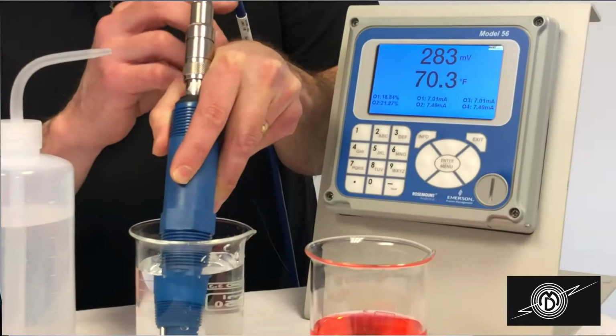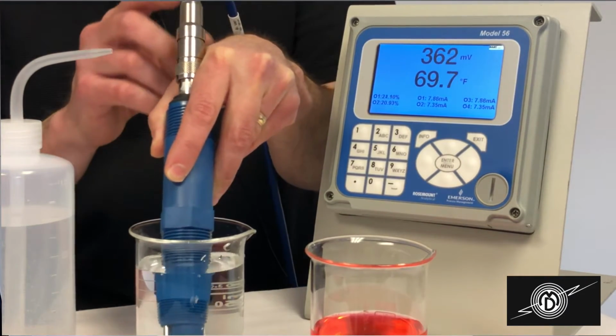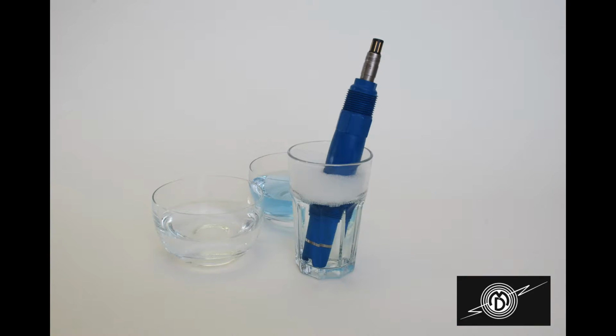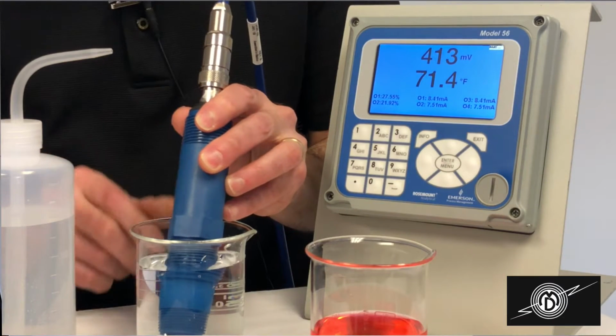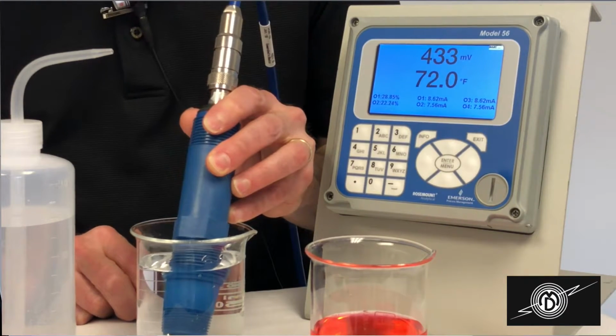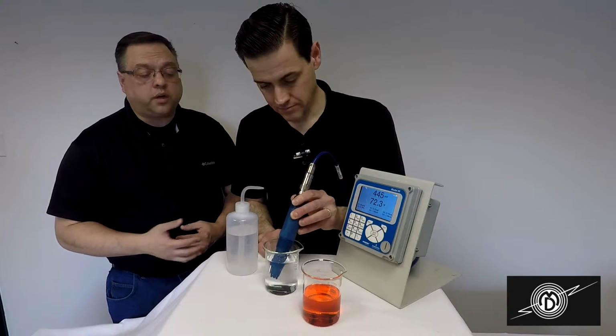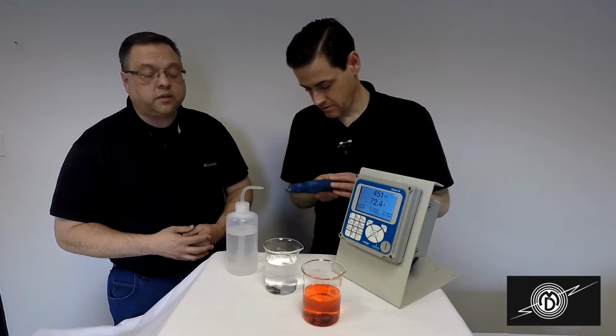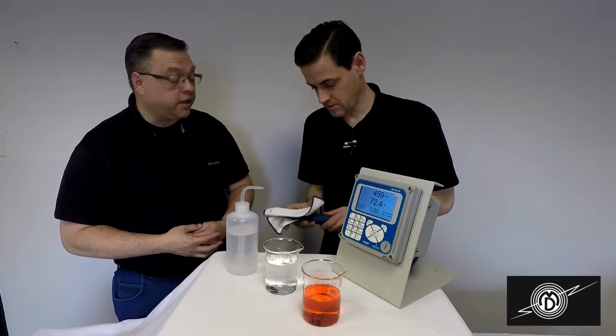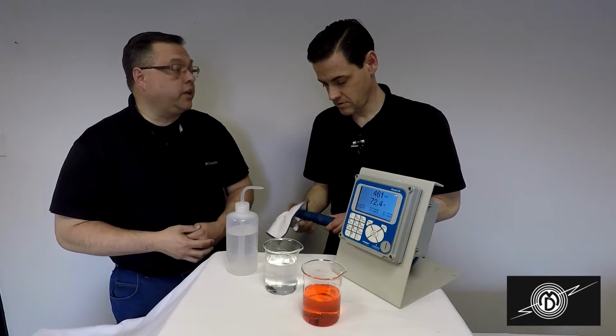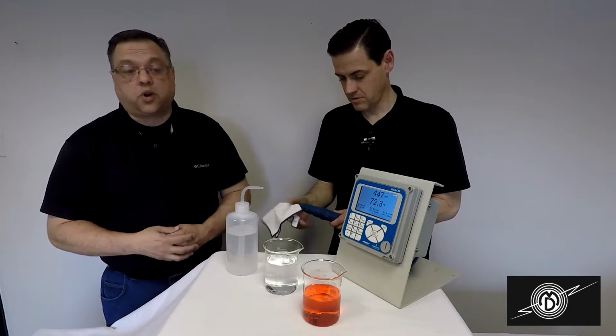Okay, now if I had buildup on there, like with a pH sensor, you'd use dish soap and soak. Correct. If there's some sort of material buildup on there, you can use some dish soap and water to clean it off, and then rinse it. Maybe even a soft bristle brush like a toothbrush, and just lightly go over that. Then rinse it and dry it off.